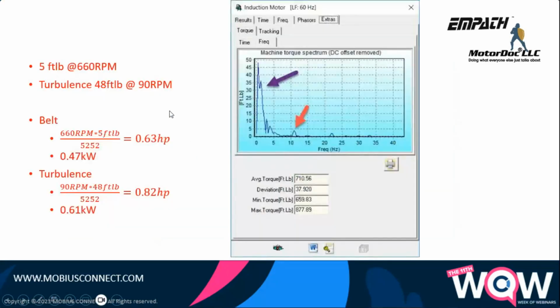So let's take a look at ESA in foot-pounds. So here's an example. These are the peaks. So if I take 5 foot-pounds at 660 RPM, going back to the torque formula, that would be 660 times 5 foot-pounds divided by 5252, or 0.63 horsepower, or 0.47 kilowatts. And then on the other one, turbulence at 48 foot-pounds. I'm just taking the one peak instead of both peaks. Technically, I should take both peaks. At 90 RPM equivalent, that comes out to 90 times 48 divided by 5252, or 0.82 horsepower, or 0.61 kilowatts.